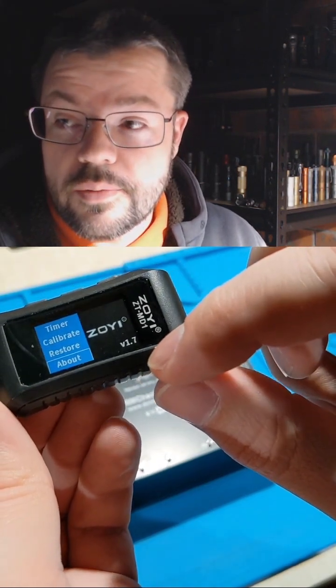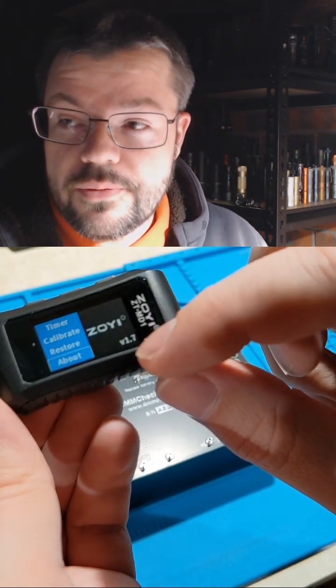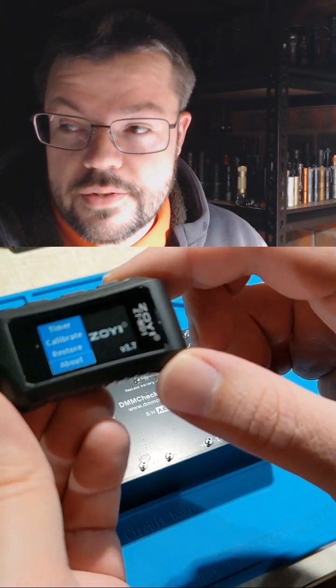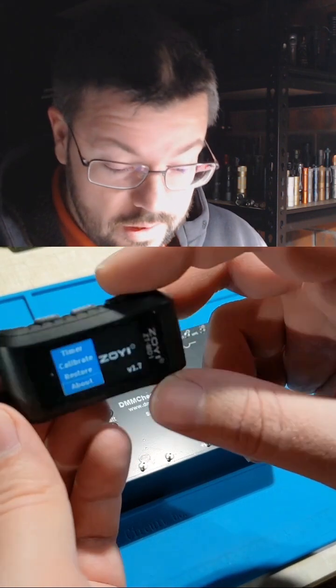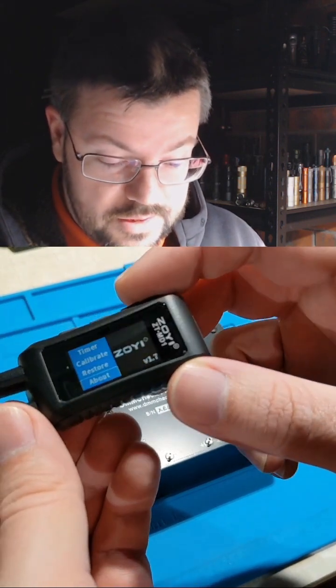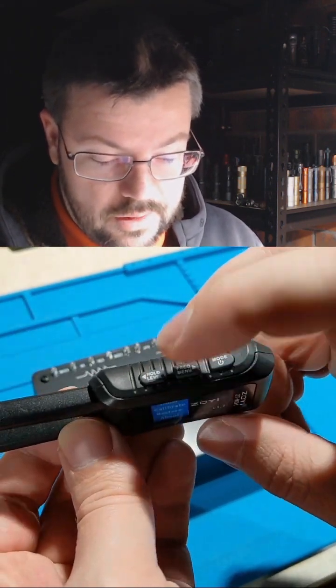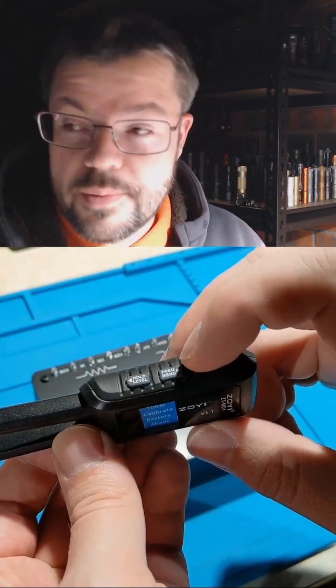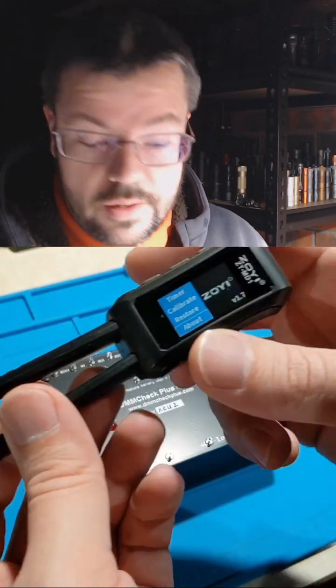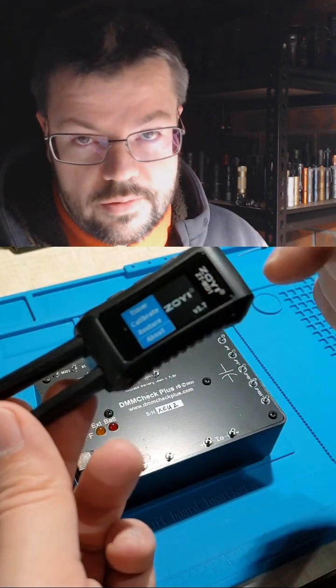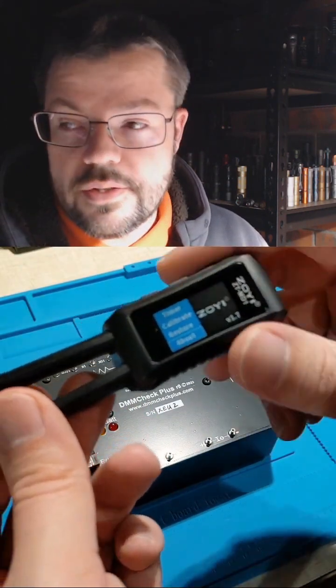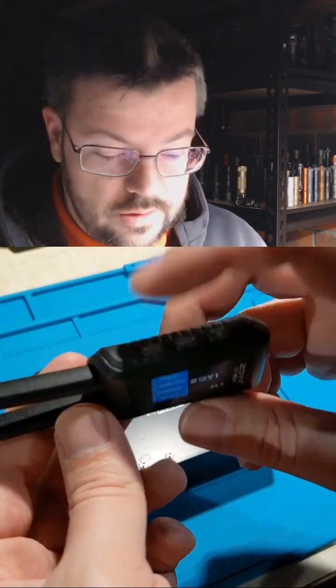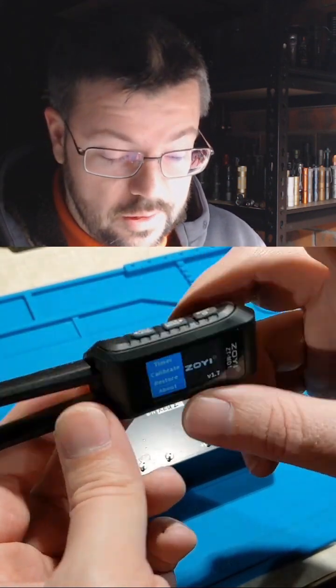It was at 1.4, 1.5, I upgraded it to 1.6 and 1.7. So 1.7 lets me press the hold button while doing a measurement, and it will record the measurement to a file. You can do data logging using the hold button.